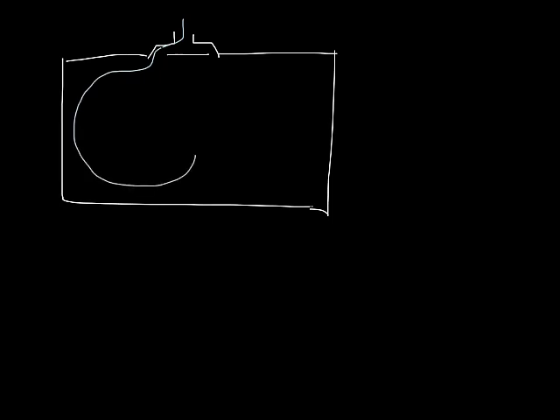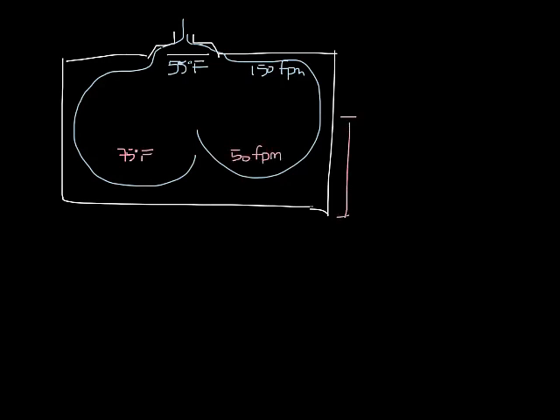So if we look at that, it looks something like this. Put a diffuser in, draw a little room, and the air is going to roll the room something like this. So what you have is 55 degree air, and it's 150 feet per minute somewhere shortly outside the diffuser. It rolls the room and mixes and becomes 75 degrees and 50 feet per minute in the occupied space.